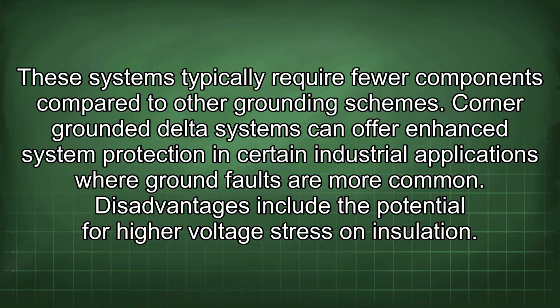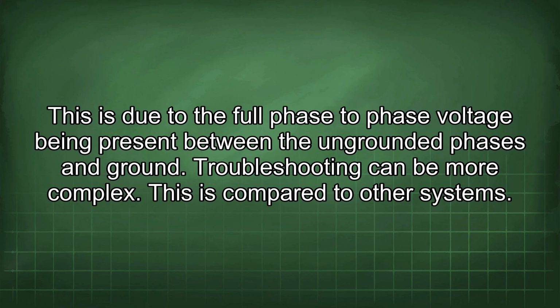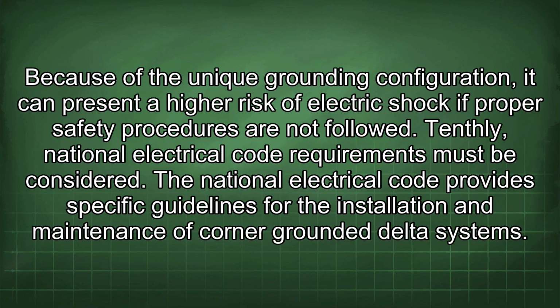Disadvantages include the potential for higher voltage stress on insulation. This is due to the full phase-to-phase voltage being present between the ungrounded phases and ground. Troubleshooting can be more complex. This is compared to other systems.